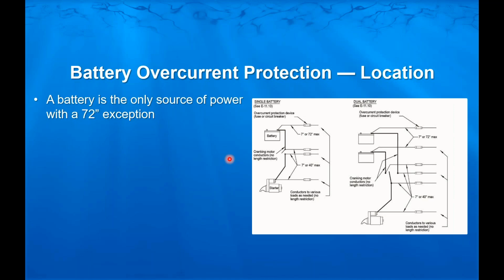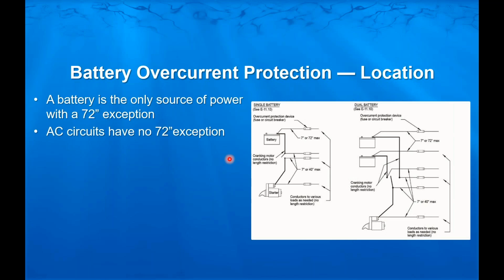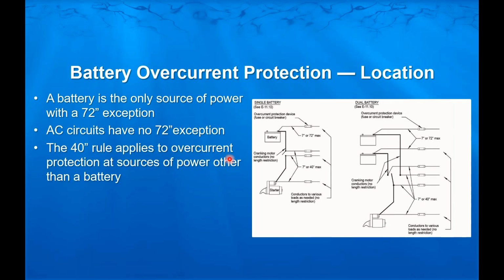So to reiterate, the battery is the only connection that has a 72-inch exception. AC circuits have no 72-inch exception. The 40-inch rule applies to overcurrent protection at sources of power other than a battery. And again, it's not 7 or 40 or 72. It's 7, or inside those longer ranges. The intent is still to get that overcurrent protection as close to the source of power as possible.